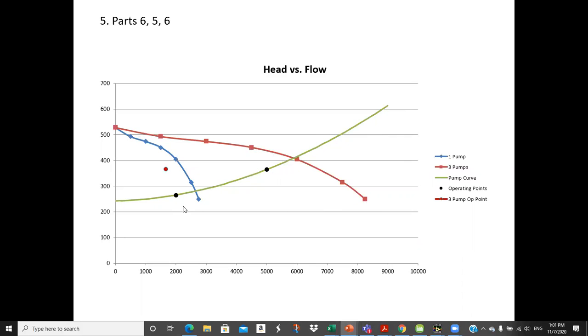And so our operating points based on the analysis would be here for 1 and here for 3. Well, at 5,000 GPM, and then this is the system curve, and these are the measured or desired flow rates, 2,000 and 5,000. And you see, if we were on the pump curve, it says this pump would be producing significantly more head. So it doesn't look quite right. And then if you take this operating point, each of the individual pumps would be back here, which you see is not on the pump curve. So it's starting to look like these pumps may be degrading a little bit.